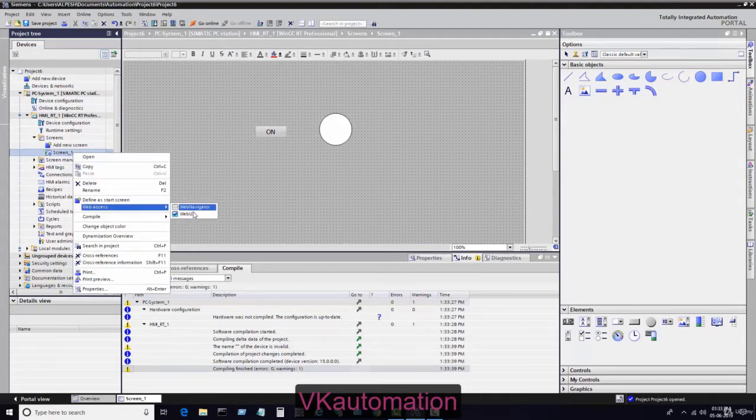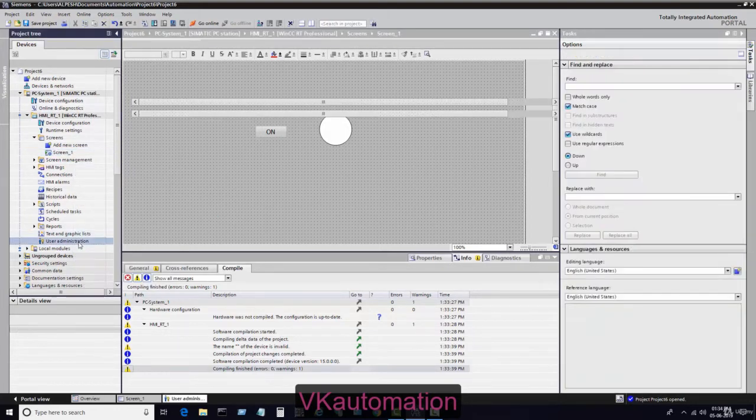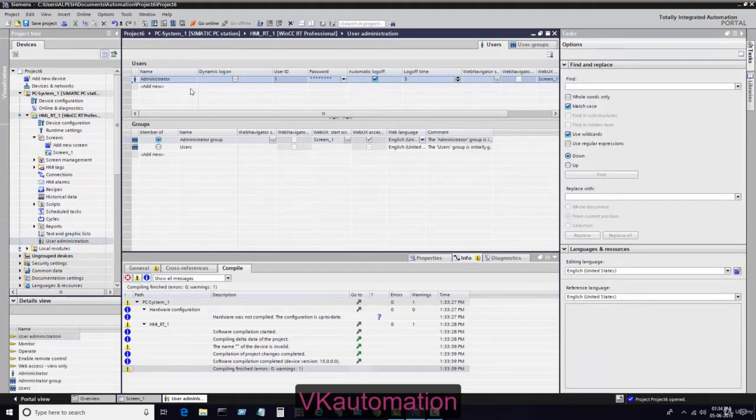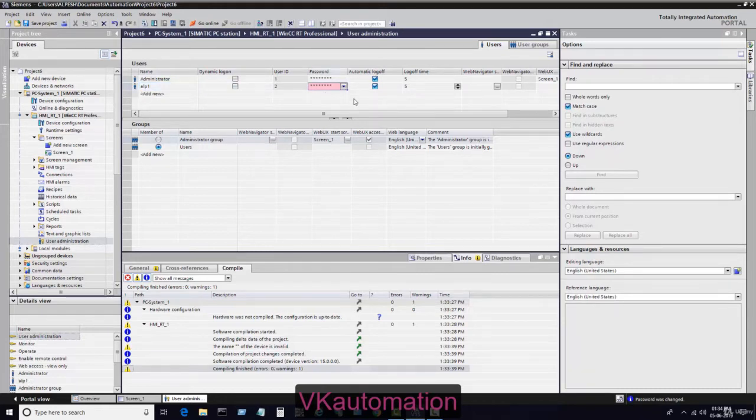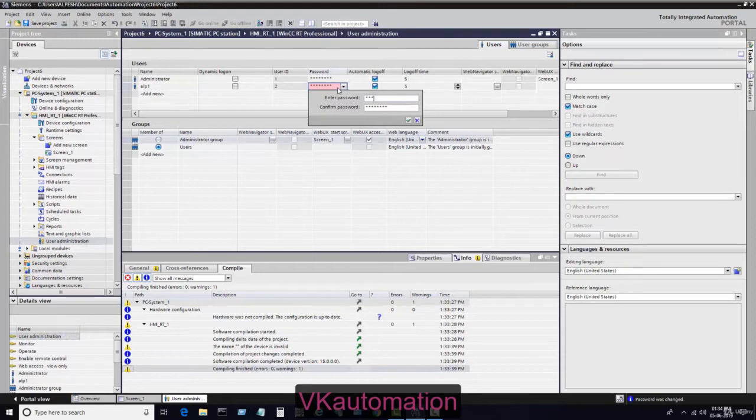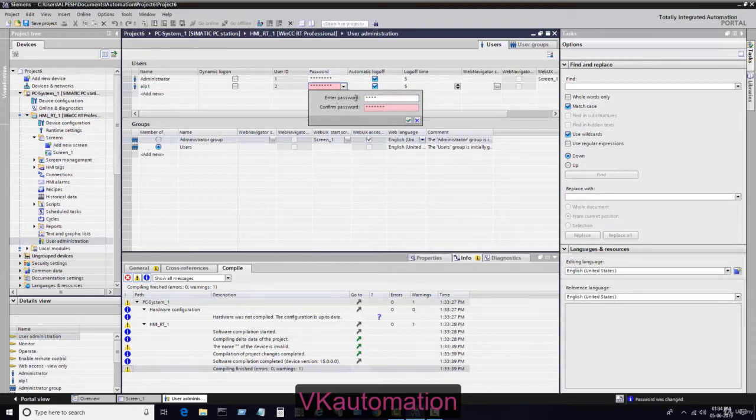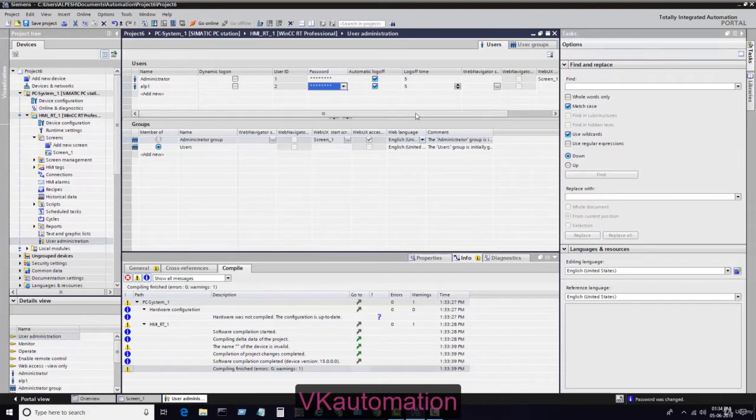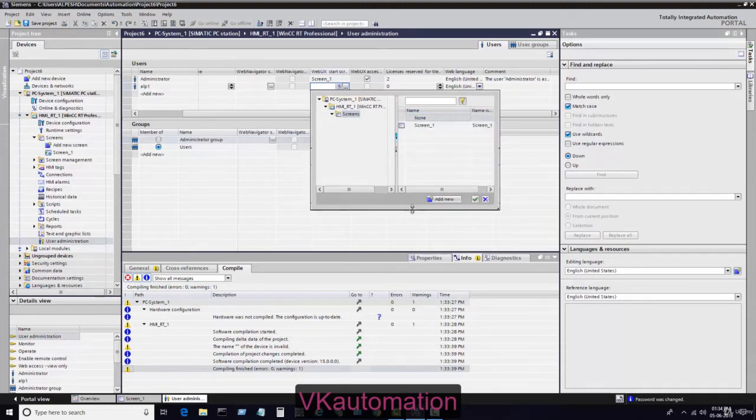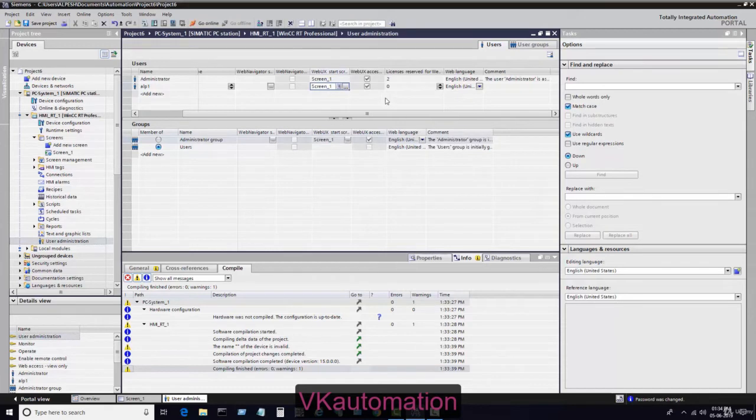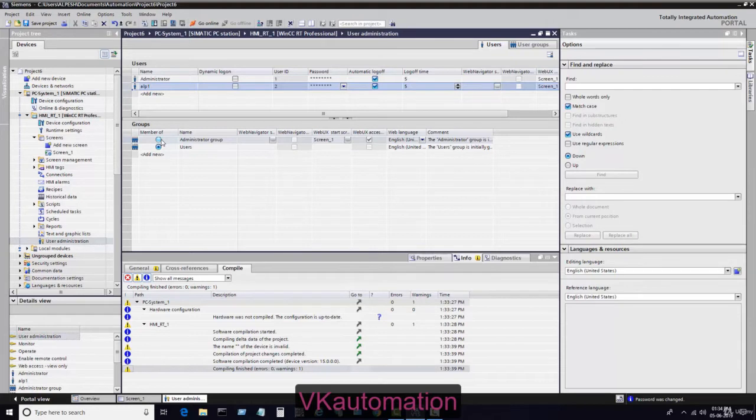I have enabled the Web UX. Now go to your user administrator, then add one new user like alp1. In alp1, assign the password. After assigning the password, you have to define the start screen of the WinCC Web UX. I define the start screen and enable the Web UX here.